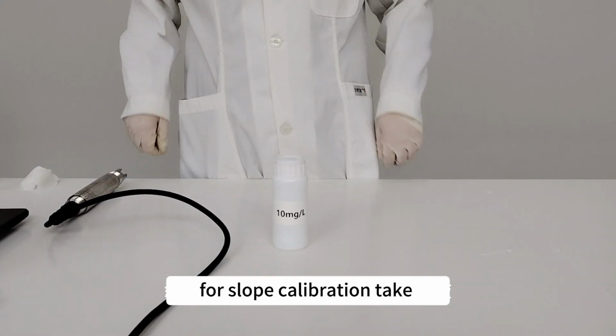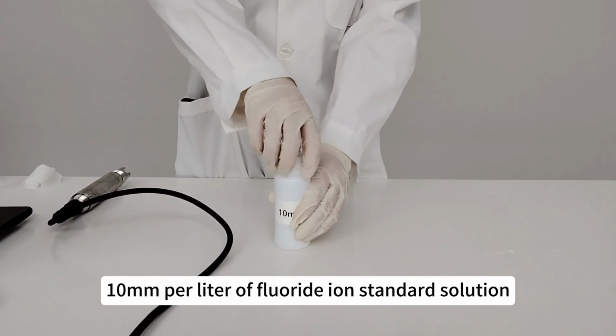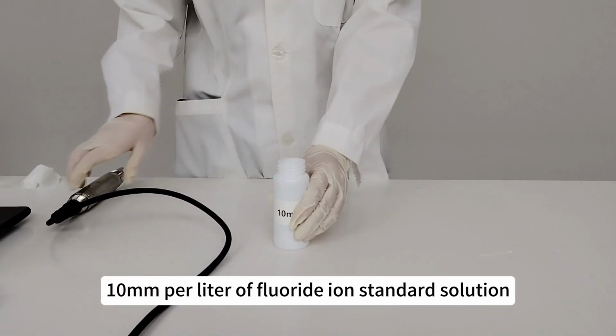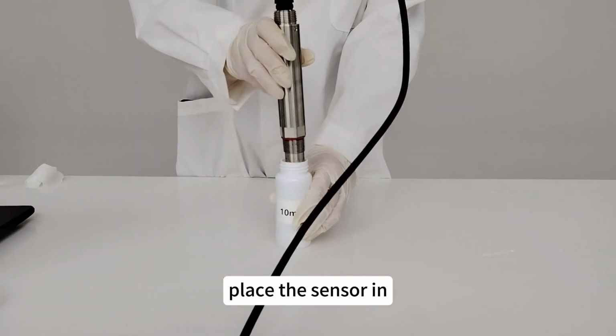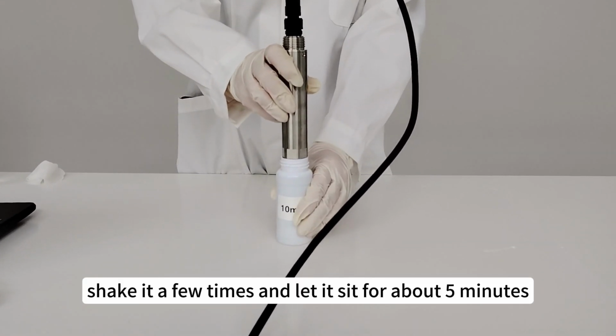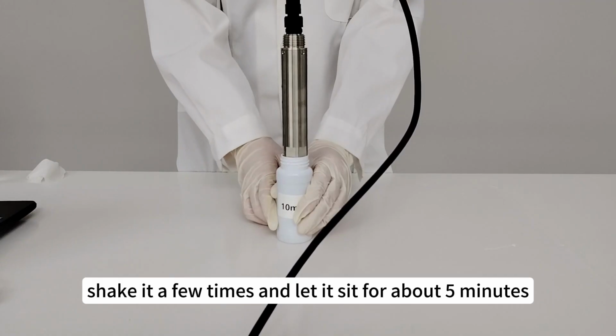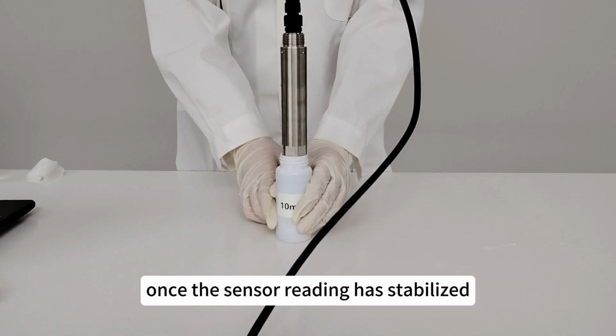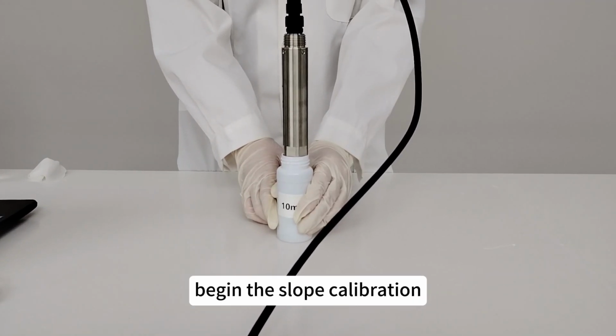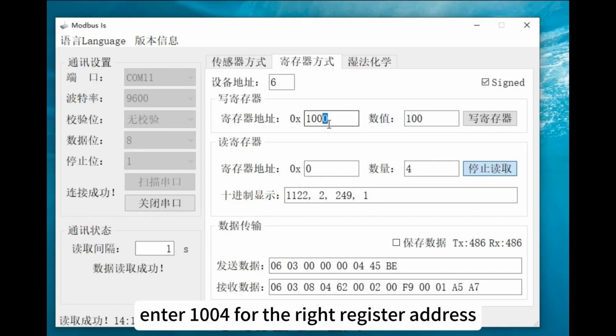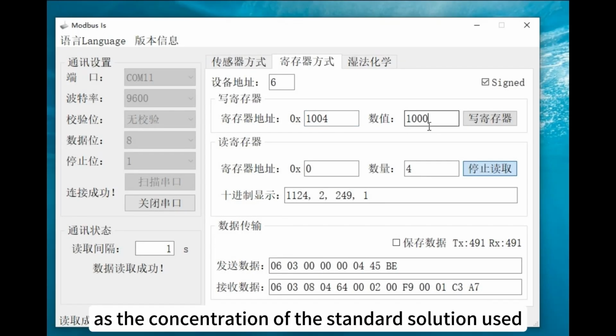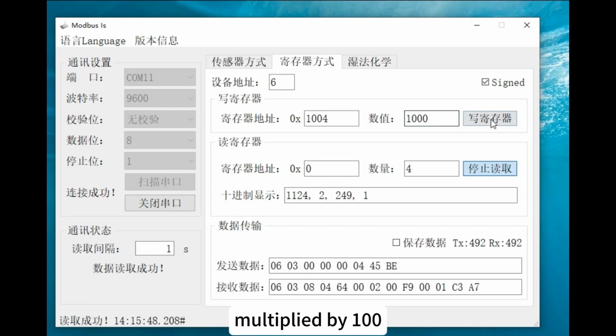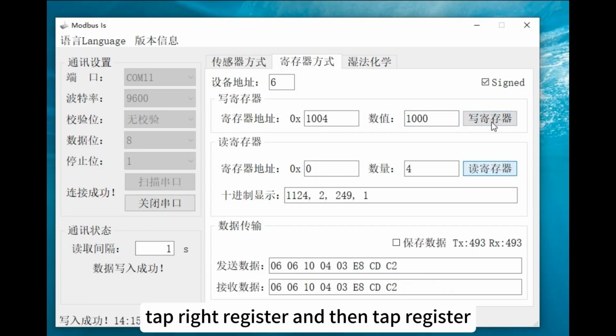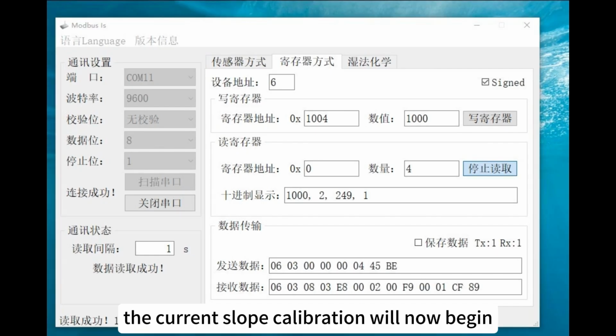For slope calibration, take 10 milligrams per liter of fluoride ion standard solution. Place the sensor in, shake it a few times, and let it sit for about 5 minutes. Once the sensor reading has stabilized, begin the slope calibration. Enter 1004 for the write register address. Write the value as the concentration of the standard solution used multiplied by 100. Tap write register, and then tap read register. The current slope calibration will now begin.